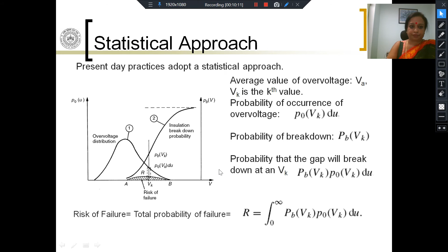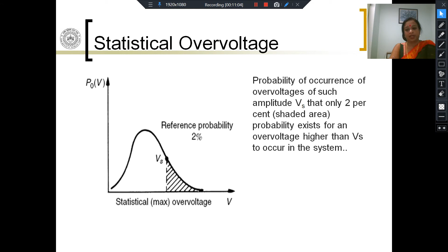So let us talk about a statistical overvoltage. The statistical overvoltage is defined as that value of the overvoltage such that the probability of occurrence of overvoltages of magnitude Vs or higher is only 2%. So this is your probability distribution curve for overvoltages, and Vs is a magnitude such that the area under this probability curve on the right hand side of Vs is only 2%. In that case, Vs is the statistical overvoltage. So by definition, the statistical overvoltage is that value Vs such that the probability of occurrence of an overvoltage of magnitude Vs or higher is only 2%, and it is given by the shaded curve.